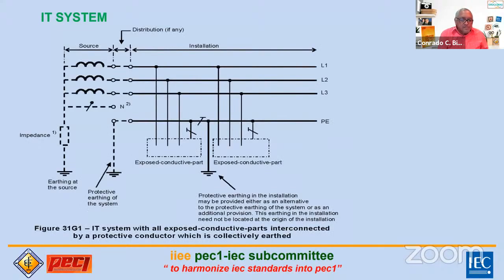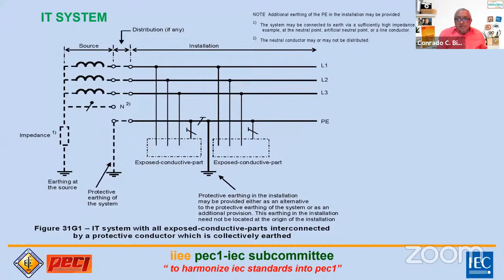Ito yung IT system. So IT system with all exposed conductive parts interconnected by a protective conductor. So hindi siya nakakonekta. Why? We can use a high impedance or wag mo siyang i-connect. So ang protective earthing mo nandito sa installation. Yung earthing system mo, hindi siya nakakonekta doon, kaya isolated ang tawag dito. Okay? Kung titignan mo parang TT pero yung neutral niya hindi naka-ground, or otherwise you use a high impedance in between, then it can be considered as an IT system or ungrounded system.